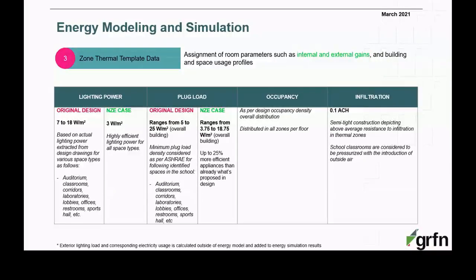As for the plug loads, the original design was around 5 to 25 watts per square meter. In the net zero energy case, we've used better, more efficient equipment, Energy Star rated, and the load reduced by around 25% on the plug loads. Occupancy was the same in both cases. For infiltration, semi-tight construction was used to determine the infiltration, and we've estimated around 0.1 air change per hour because the building is supposed to be pressurized with outside air.